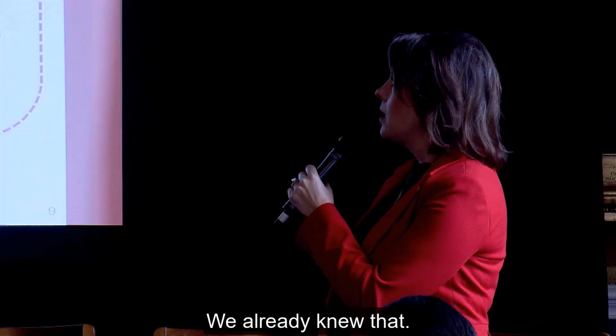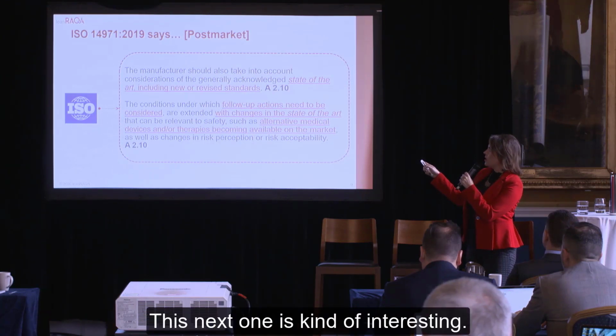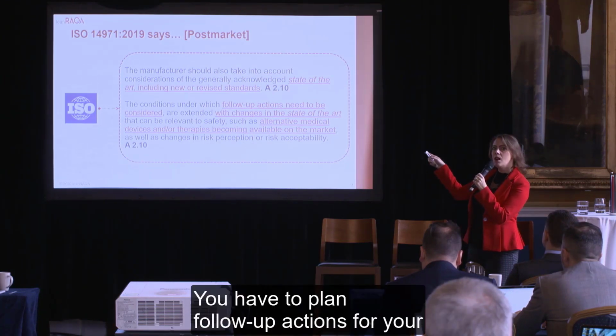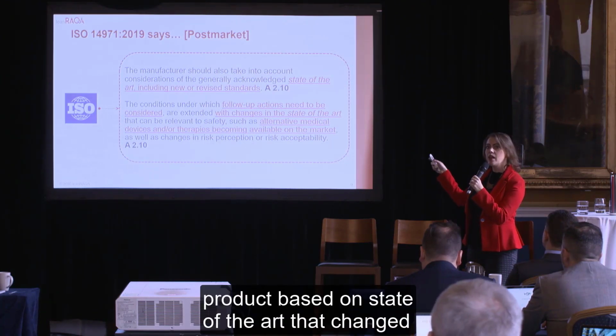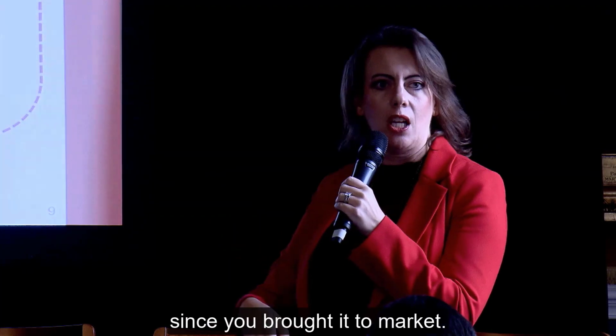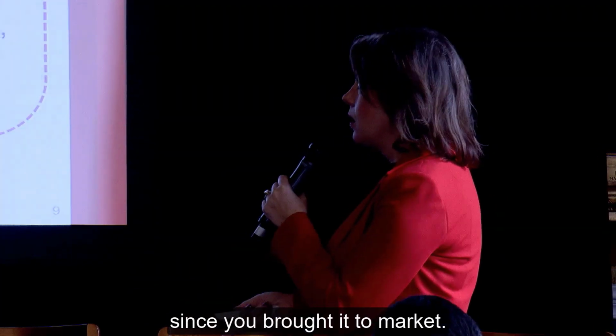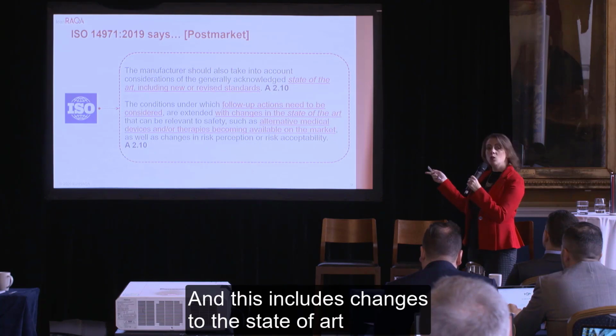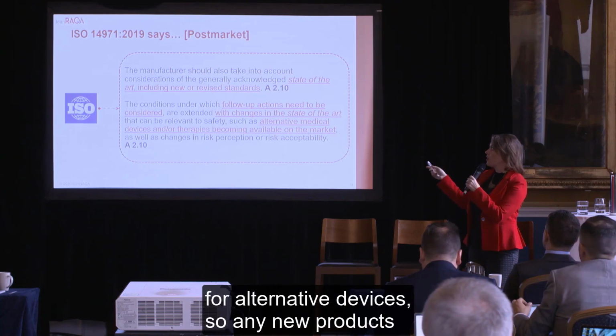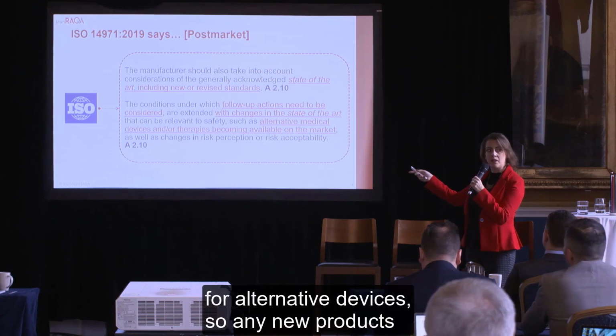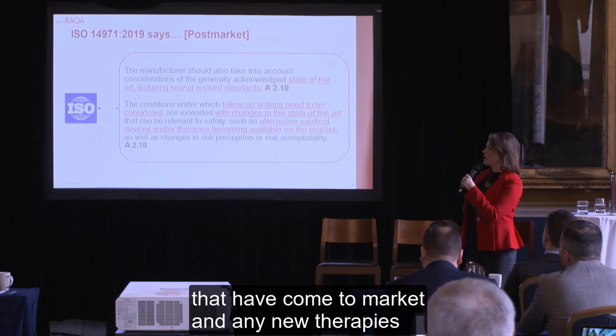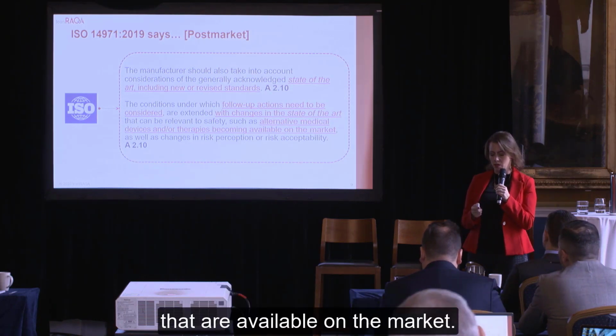We already knew that. This next one is kind of interesting. You have to plan follow-up actions for your product based on state of the art that changed since you brought it to market. And this includes changes in state of the art for alternative devices, so any new products that have come to market, and any new therapies that are available on the market.